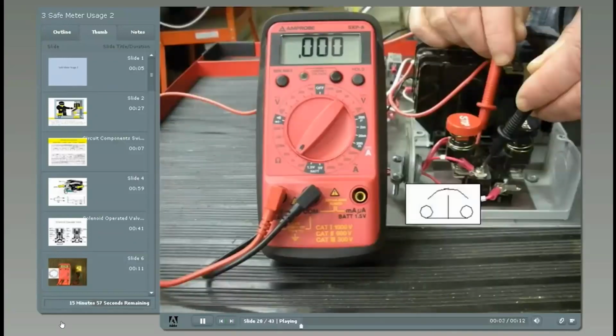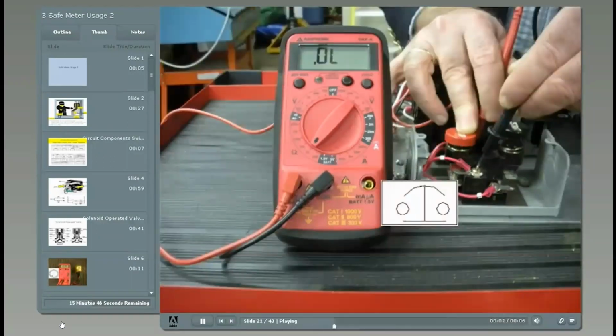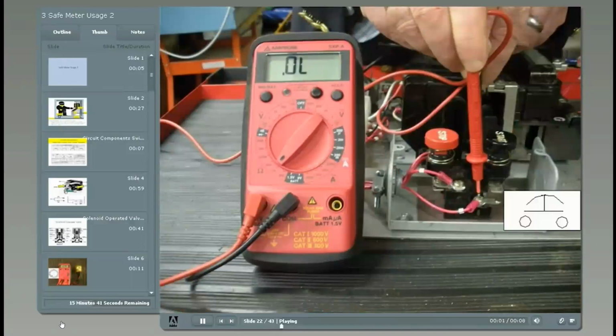This stop switch has normally closed contacts and the ohm meter reads 0 ohms. If the selector was set to continuity, the beeper would be chirping. The contacts are actuated, and therefore the ohm meter reads infinite resistance.